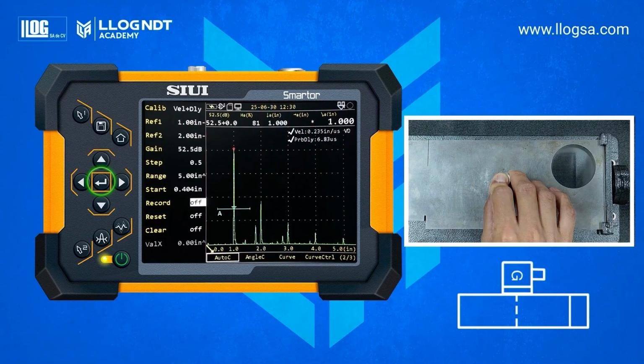Once the calibration is complete, the instrument will display the velocity and delay values of the transducer. Verify that the distances are correct. 1 inch and 2 inches. With this, we complete the calibration using a dual-element transducer.